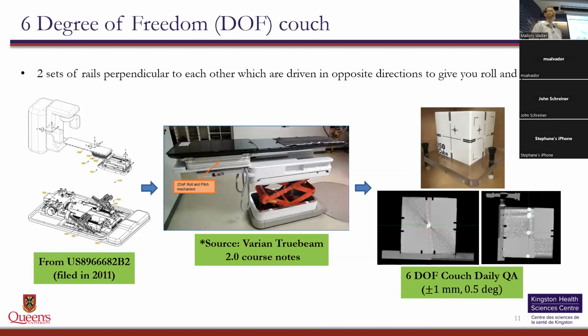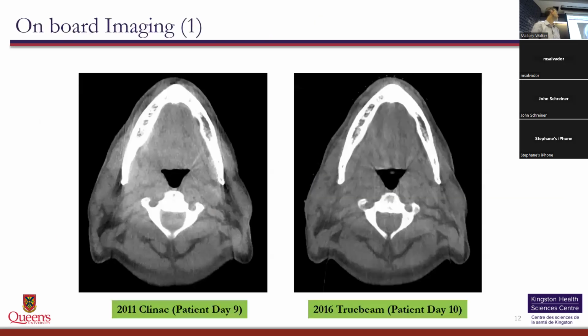The couch now has two programmable perpendicular rails where we're able to not only rotate the patient, but also roll and pitch the couch so that we can basically align the position of the patient perfectly with our planning CT in a 6-degree of freedom match. Our daily tolerance is 0.5 degrees and a millimeter, but we can actually do better than that. That's just a check that everything's good. It doesn't yield exciting results.